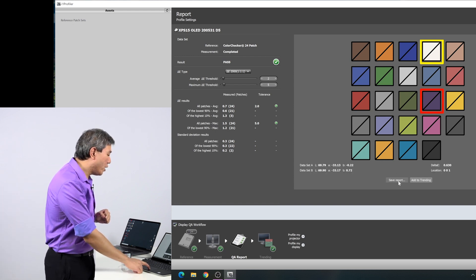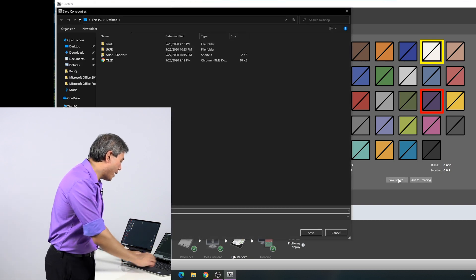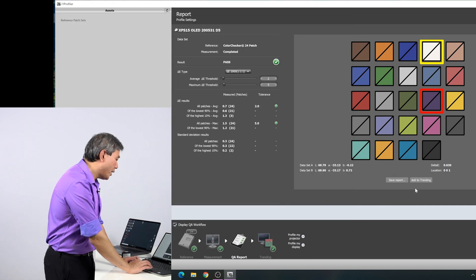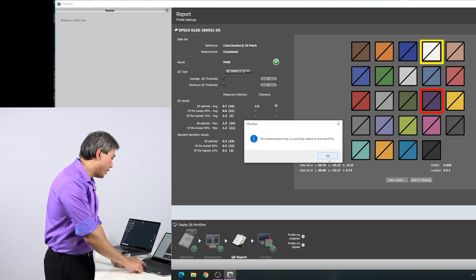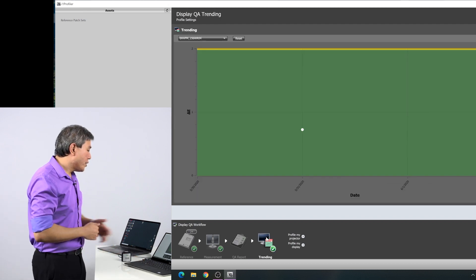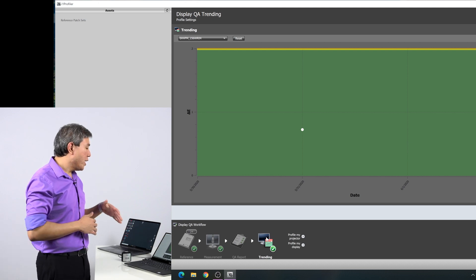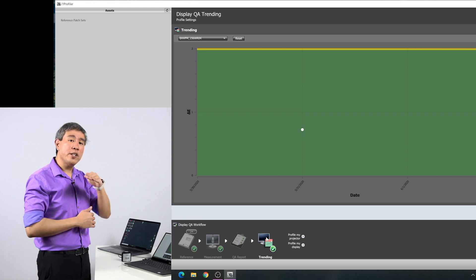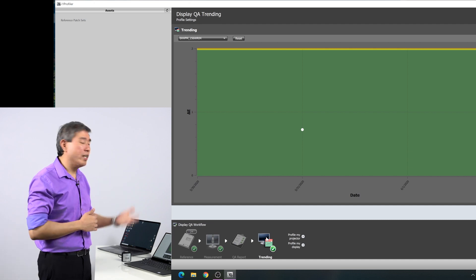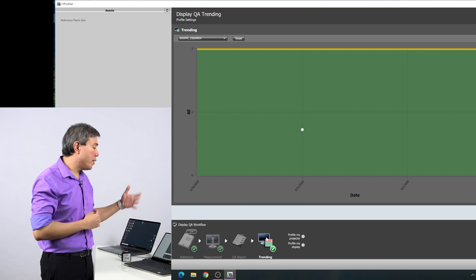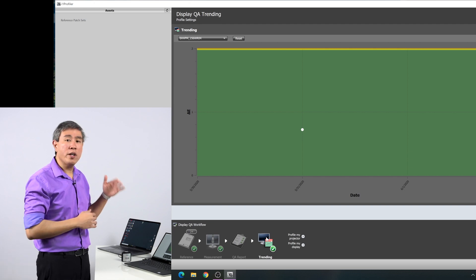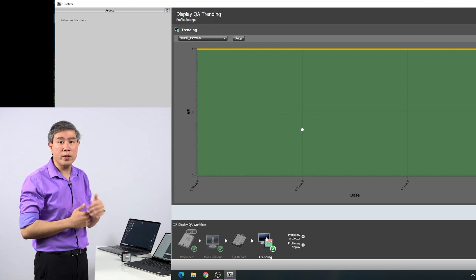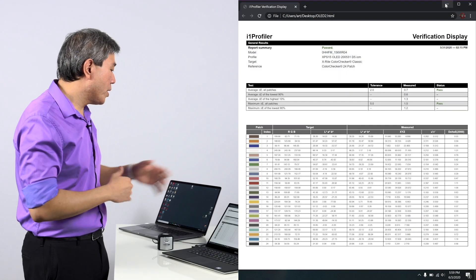From here, you can also save this report out. It will save it as an HTML file. And the other thing you can do here is add this to trending. So I'll click add to trending. In trending, it just puts one dot there because I only have one calibration so far. Essentially, over time, what you want is either the trending to be straight or going down. If your trending start to go up, that could be an indicator that something is starting to happen in your display with the backlight technology. If your trending is going up, what I would do is recalibrate to see if the trending would come down in the next calibration. Let's take a look at the report.